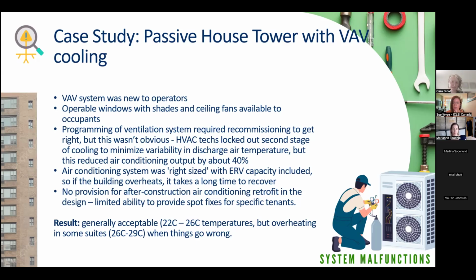Initially, people were complaining a lot on the operations side because the temperature of the makeup air unit fluctuated a lot. So to deal with that, an HVAC tech at some point locked out half the cooling capacity, which reduced the variation because we weren't getting as much cooling. That worked until our first heat wave, when the system wasn't outputting enough cooling. But because it was so small in the first place, it never occurred to the owner that the system could be underperforming.